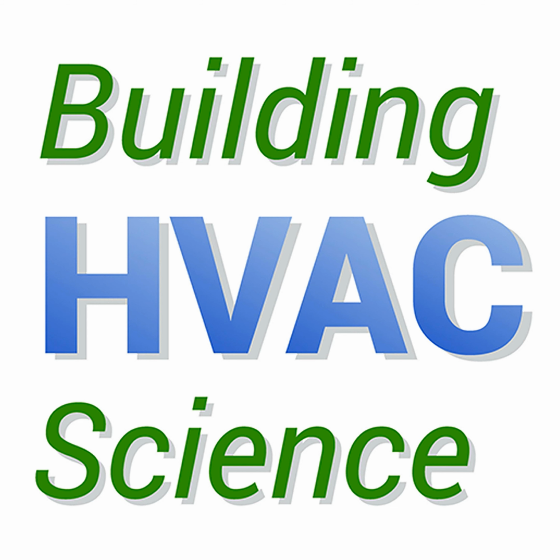To sell a DOAS today, your ISMRE needs to remove 3.8 pounds of water for every kilowatt hour. Our units, depending on your airflow and where you specify it, run from 9 to 11. So we're almost triple the standard. We find that we're about 50% to double what you're going to get from your typical vapor compression system today, which is why we get those great energy savings at 30 to 50% that I mentioned earlier. Wow. The magic's in the liquid.